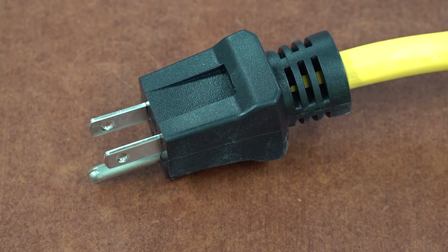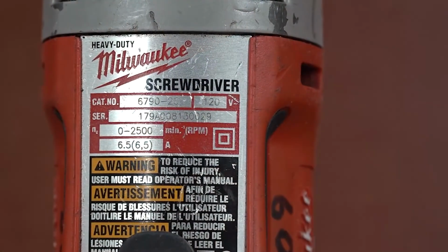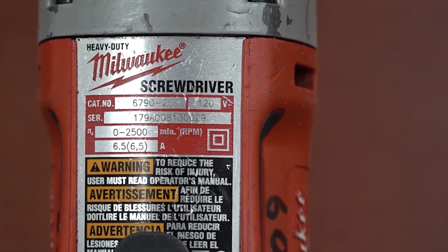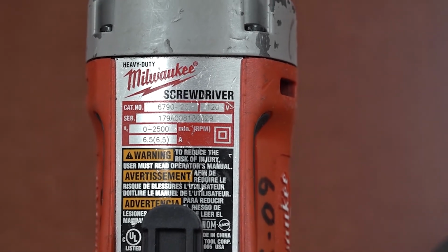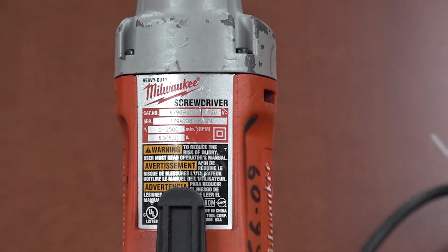Page 13 of the Standards of Excellence Pocket Guide discusses portable hand tools and says they shall meet one of the following requirements. They must be equipped with a 3-wire cord with the third prong being grounded. They must be of the double insulating type, which is identified by a square within a square symbol. Or they must be connected to an isolating transformer or source, which is not very common at Cook. Or they must be connected to a power supply protected by a GFCI.